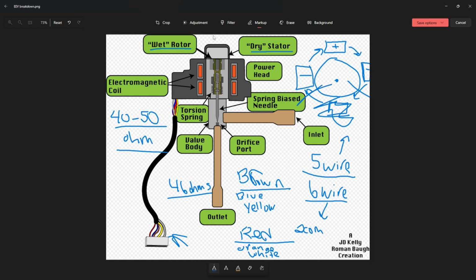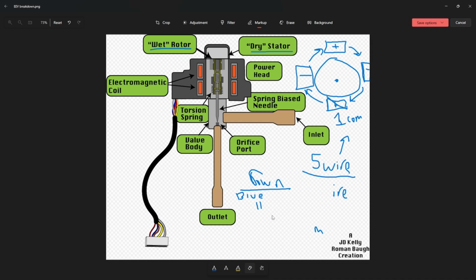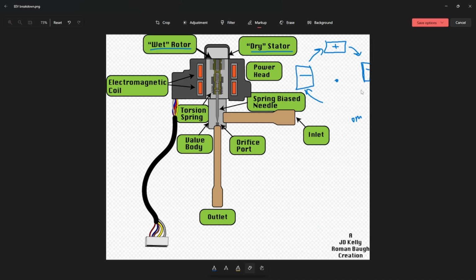All right, so now we've covered the electrical troubleshooting on this stuff. And same thing as the sensors, I'm just going to go ahead and erase this stuff instead of going back through all of it. So same thing as when we're testing the sensors' resistance: when you're testing the resistance of the stepper motor, you should not get any continuity to ground on any of this stuff you're testing. And remember, resistance checks have to be done with the plug removed from the board. So the Molex connector has to be off of your board to do a proper resistance test, because you want to isolate the stepper motor and only see what the coils are giving you for resistance. You don't want any backfeed from our board, which you will get if you try to test it plugged in.